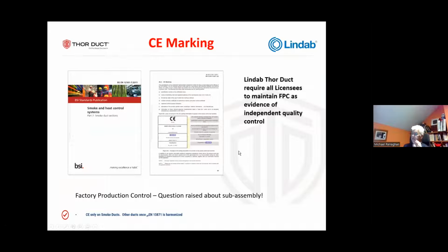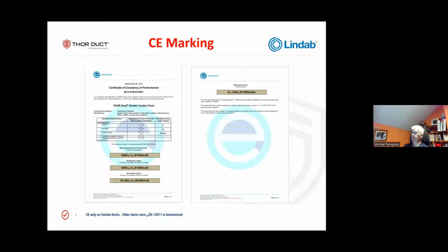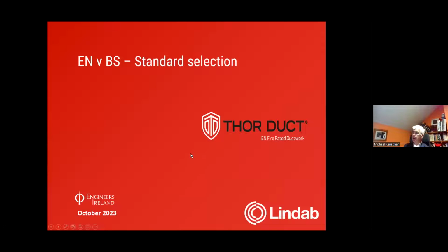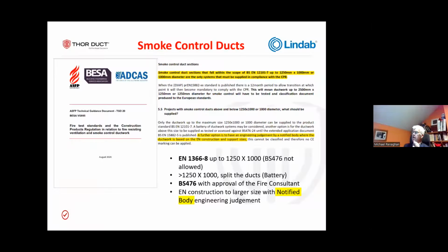Okay, so that's the CE marking. As I say, under Regulation 305, it is the law. It should be there. You need to just double check that it's available. And again, documentation will be provided for that by a third notified body. Now, EN and BS standards, there's a bit of a clash here. So there was a document, which again is available to you and is going to be provided later, which was the Technical Guidance Document number 20 issued by ASFP, BESA and ADCAS. It was published to deal with the questions that were arising. So let me just summarize it in very simple terms.